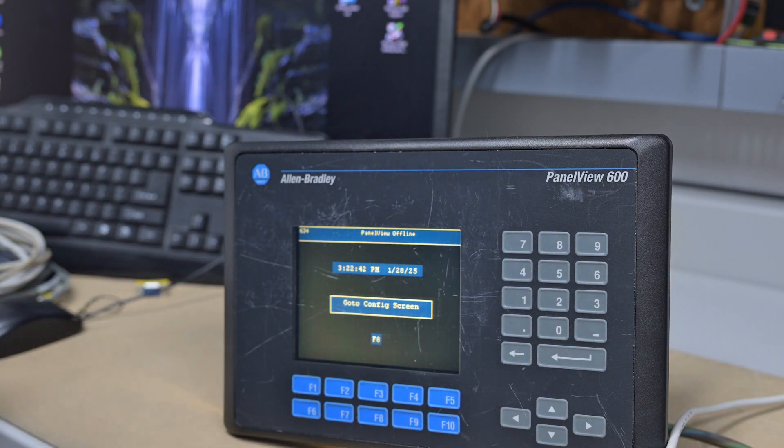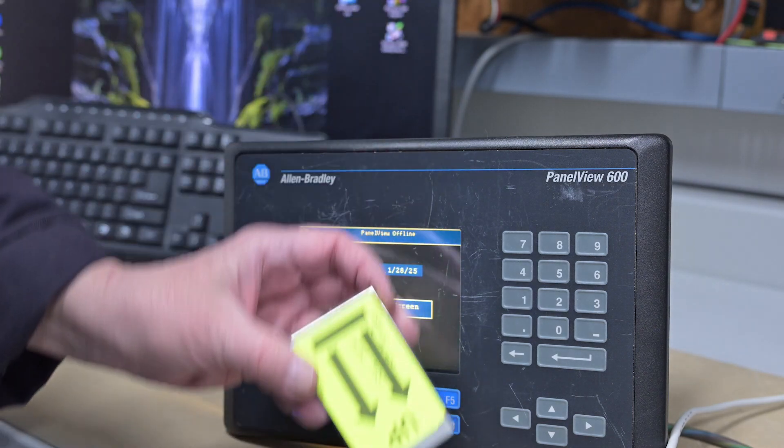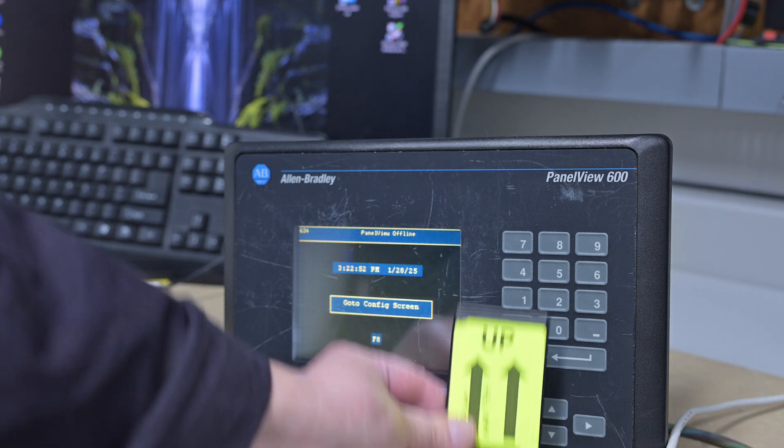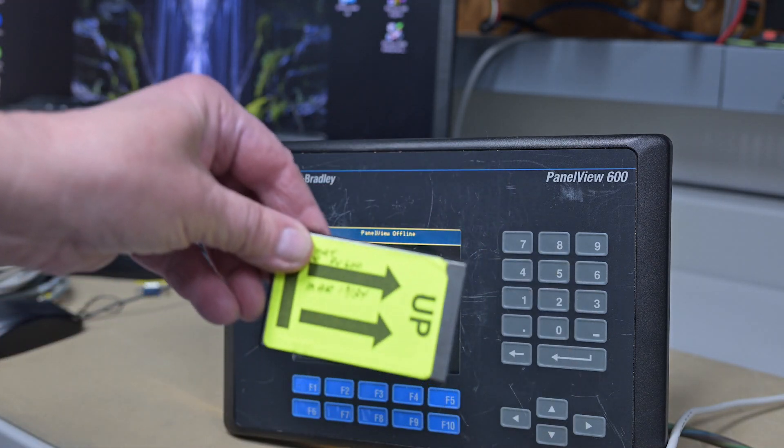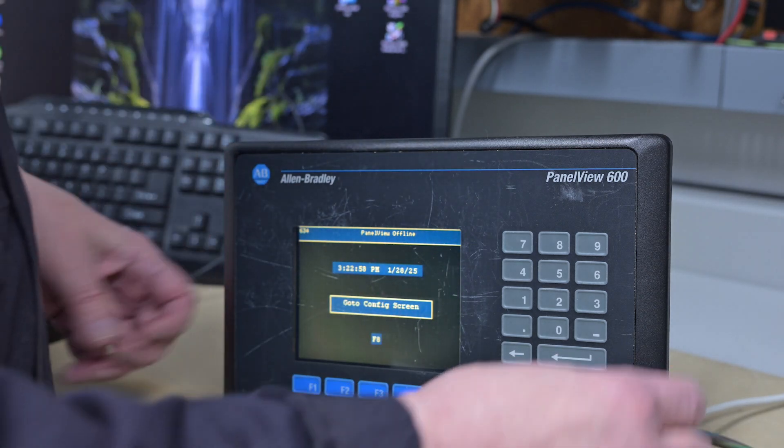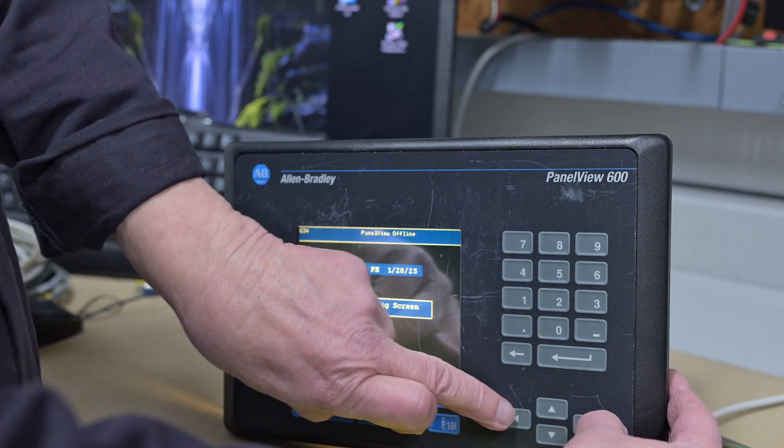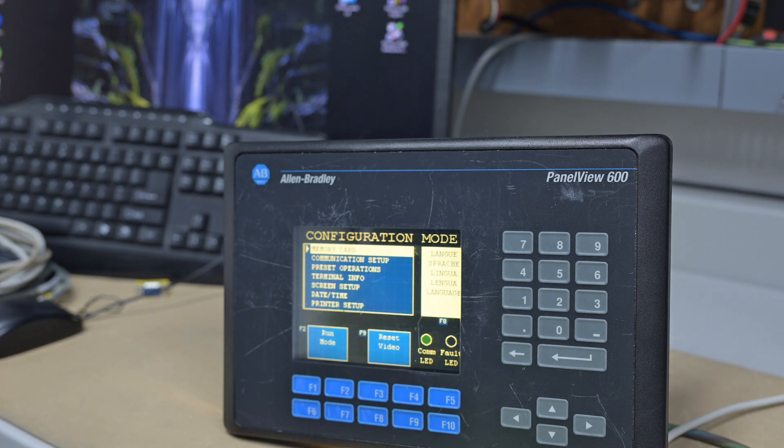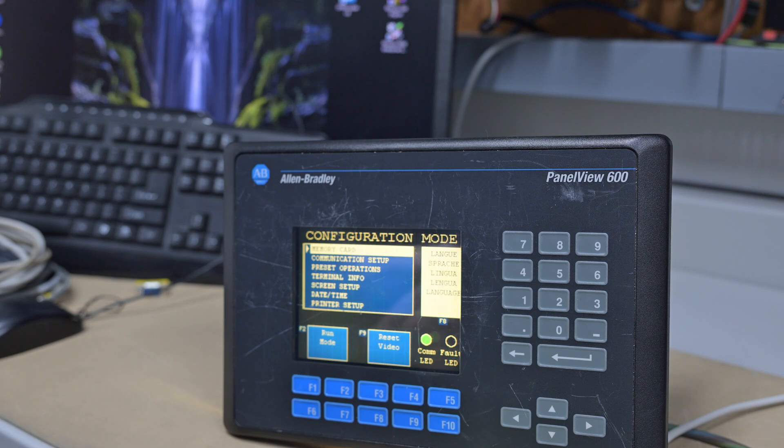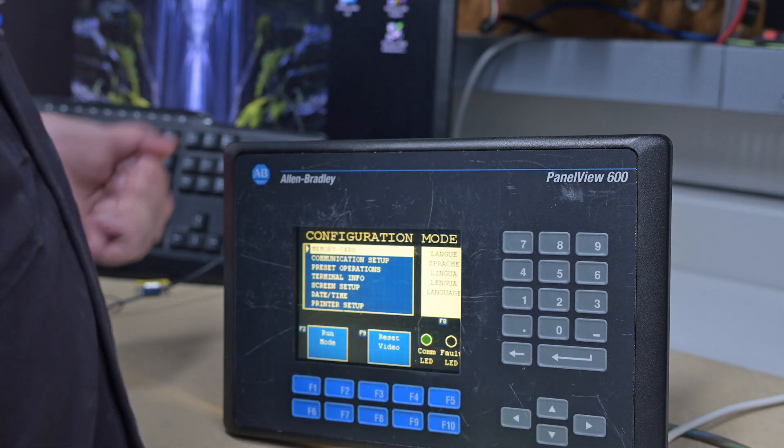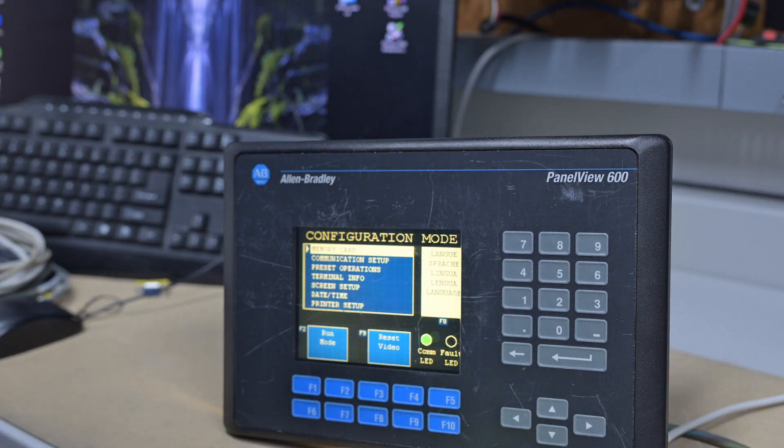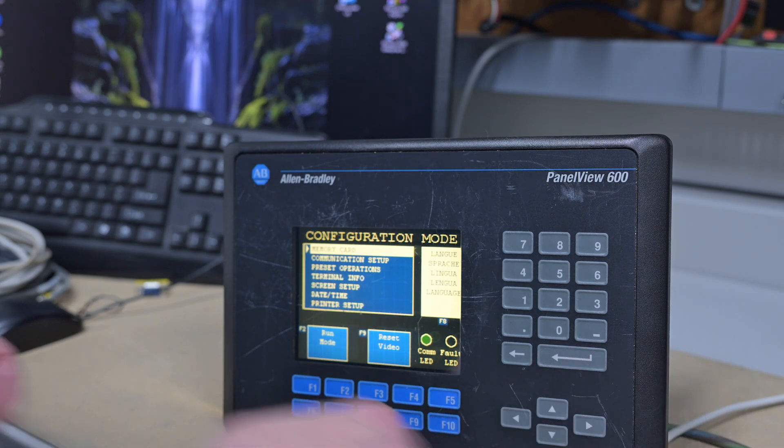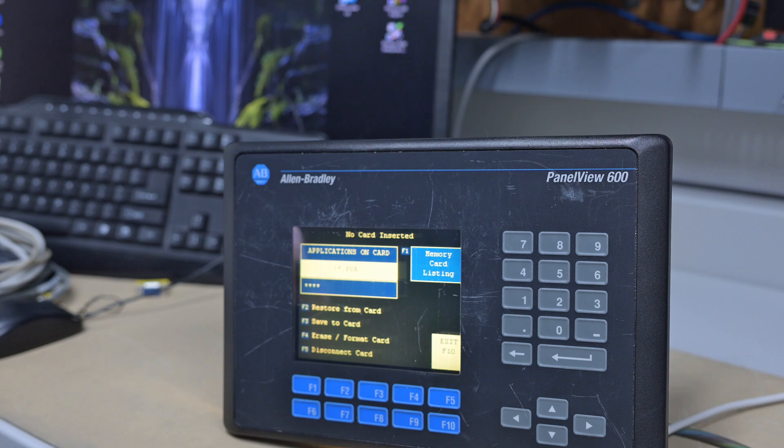So now what we're going to do is we have a PCMCIA communication card. And it says up, but that's a relative term. So what we want to do is either in this case we just press F8 or you hit your left and right arrow at the same time and it takes you into the configuration screen. Now this trick also works on the newest, latest and greatest Panel Views and Panel View Plus Seven and Six as long as you've got the arrows to work with.